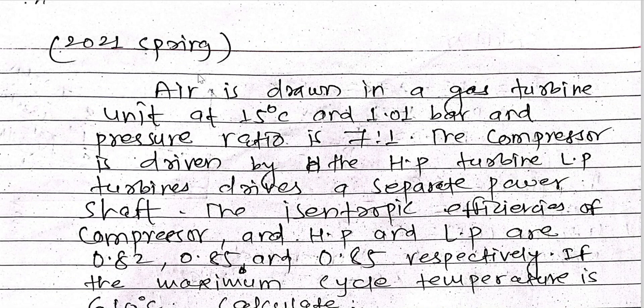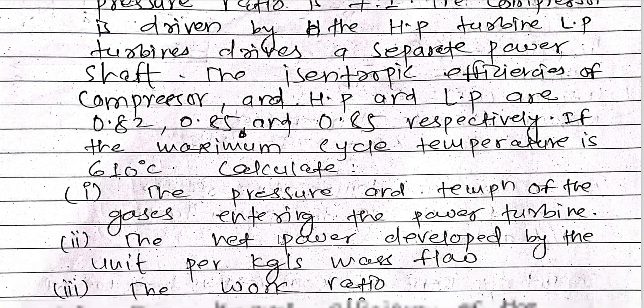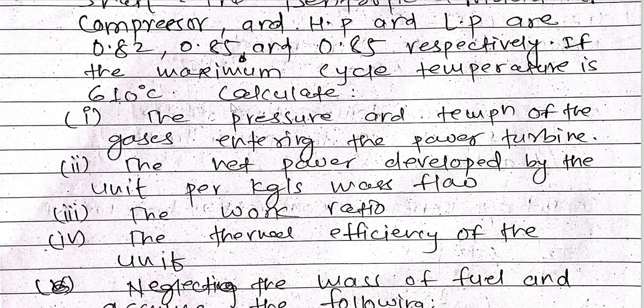Welcome to the numerical series on power plant equipment. This question is from the 2021 spring exam of Pokhla University. Air is drawn into a gas turbine unit at 15 degrees Celsius and 1.01 bar pressure. The pressure ratio is 7:1. The compressor is driven by the HP turbine, and the LP turbine drives a separate power shaft. The isentropic efficiencies of the compressor, HP turbine, and LP turbine are 0.82, 0.85, and 0.85 respectively. The maximum cycle temperature is 610 degrees Celsius. Calculate the pressure and temperature of the gas entering the power turbine.